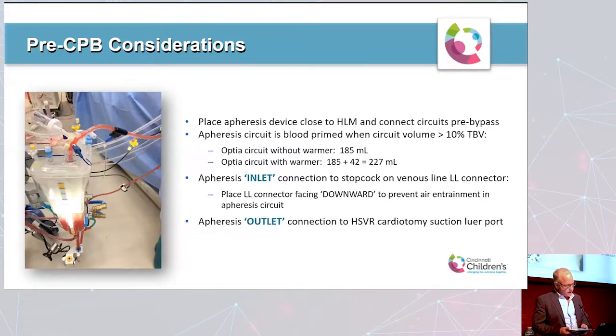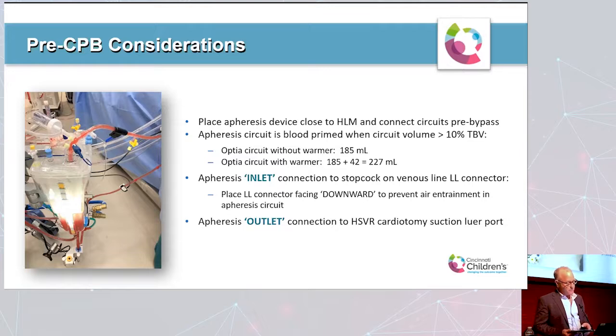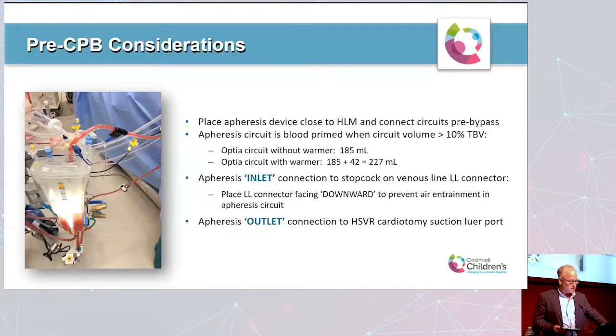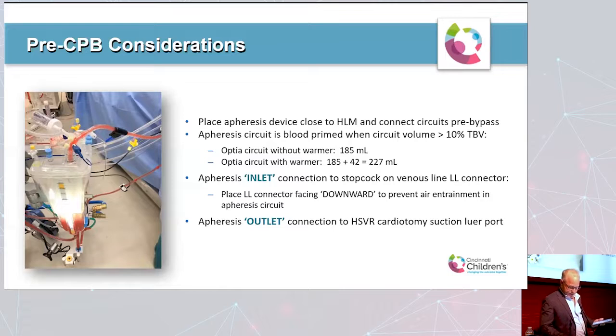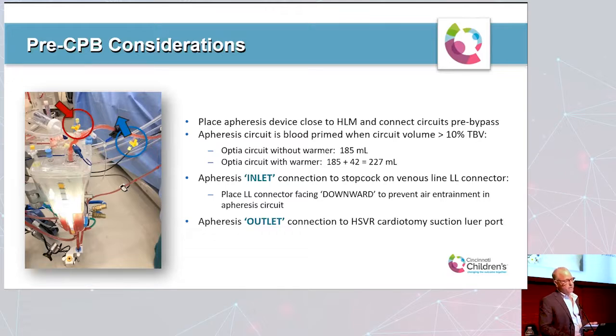For pre-bypass considerations, we place the apheresis device close enough to the heart-lung machine to connect the circuits. The apheresis circuit is blood-primed when the circuit volume is greater than 10% of the patient's total blood volume. With the Optia, the circuit volume is about 185 cc without a warmer; with a heat exchanger it adds 42 mL for a total prime of about 227 mL. The inlet connection to the apheresis device is a stopcock on a Luer connector on the venous line; the outlet returns to a Luer port on top of the hard-shell venous reservoir.